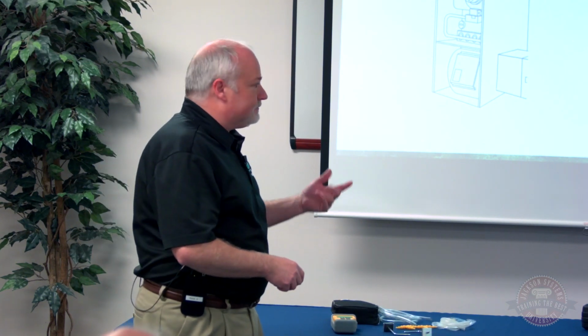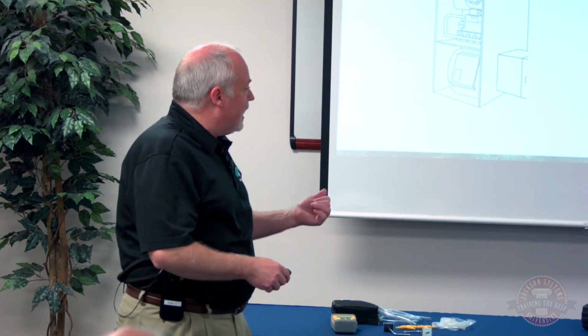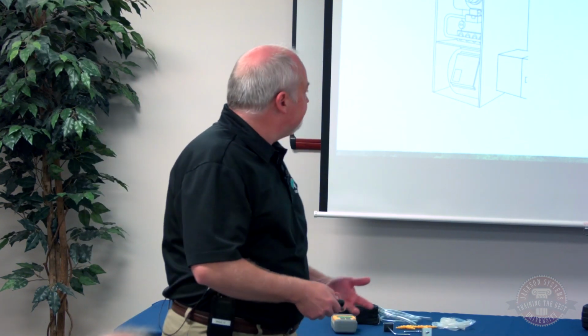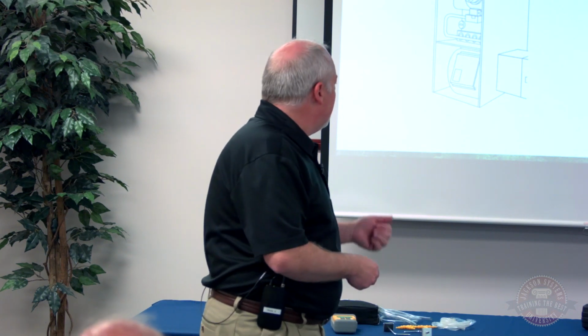Maybe we've got a bird's nest that's in our vent cap. Maybe we've got a draft inducer that, maybe it's an older one with the metal blower wheel and that wheel's rusting and coming apart, for some reason. Maybe the motor's starting to hang up and get dirty or what have you. So there can be several reasons we need to figure out why do we have poor draft in that piece of equipment.